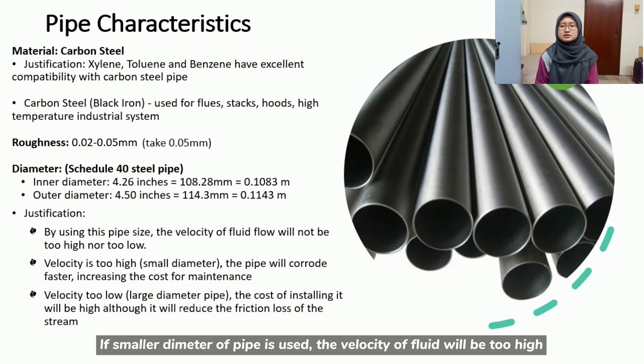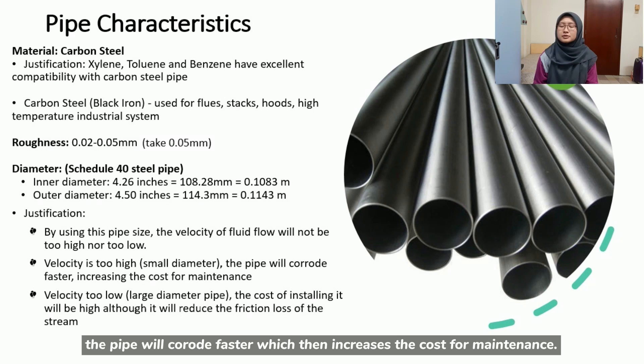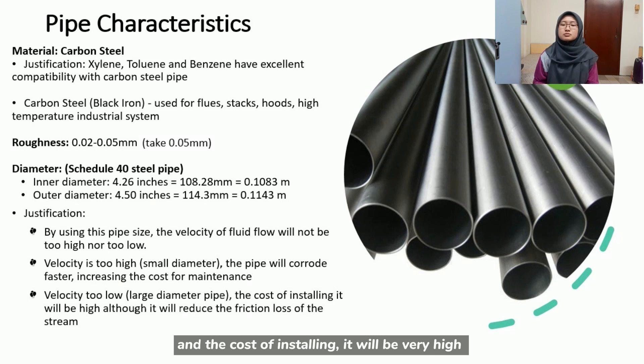If smaller diameter of pipe is used, velocity of fluid will be too high, the pipe will corrode faster which then increases the cost for maintenance. If larger diameter pipe is used, velocity of fluid will be too low and the cost will be very high although the friction loss of the streams is reduced.